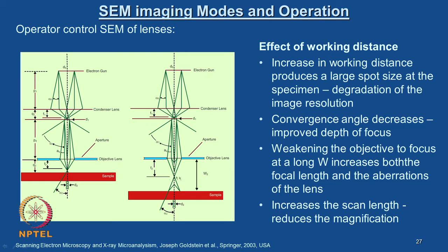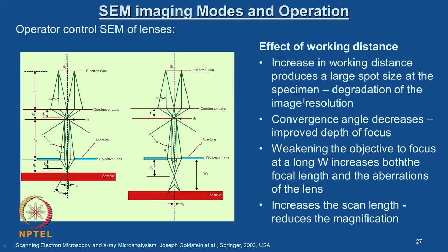The convergent angle decreases with increased working distance, which results in improved depth of focus. Increasing working distance also weakens the objective to focus at a long working distance W, which increases both the focal length and the aberrations of the lenses. This also increases the scan length and causes reduction in magnification. This is an important parameter the operator can control and make appropriate decisions depending on what information is being sought from the specimen surface.